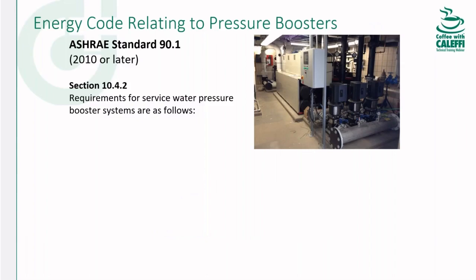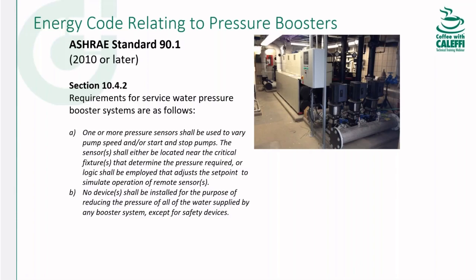We've got the energy codes, ASHRAE 90.1. Yeah, so those of you that are required to follow ASHRAE 90.1 energy standards for plumbing systems, section 10.4.2, it's only got three requirements. Use a remote sensor to compensate for the friction loss difference between the pumps and the remote fixture, or use pump software that does that, which most manufacturers today that sell variable speed boosters have, and it will reduce the pressure with reducing flow. So either remote mount the sensor or use the software.